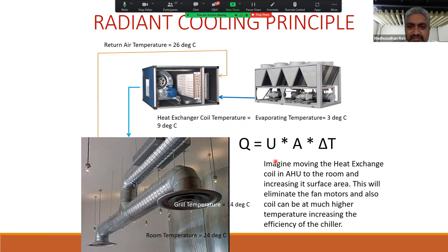So if you look at this equation, the total heat transfer is heat transfer coefficient times surface area multiplied by delta T or LMTD, whichever, right? Here you will see LMTD will be large, and that is the reason why you need 7 degrees centigrade chilled water to maintain 24 degrees centigrade. But if you increase the surface area, your LMTD can come down for the same amount of heat transfer. So therefore, in radiant cooling, you can supply water at 15 or 16 degrees and still maintain 24 degrees centigrade.